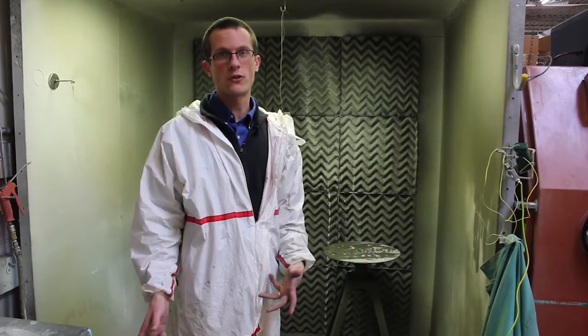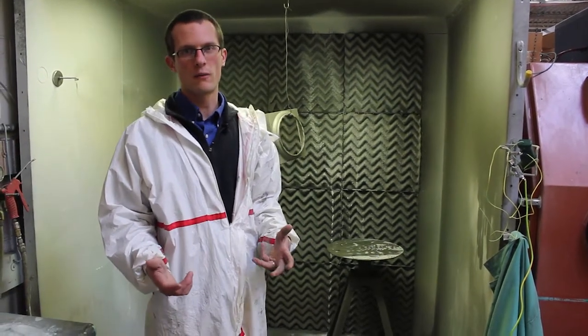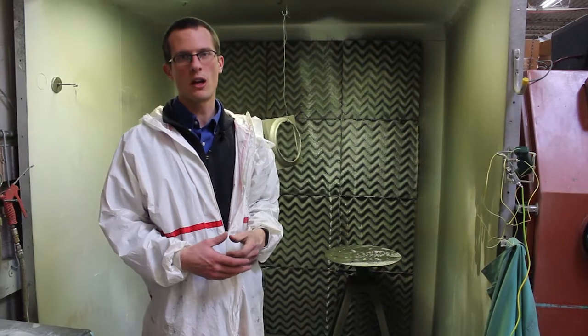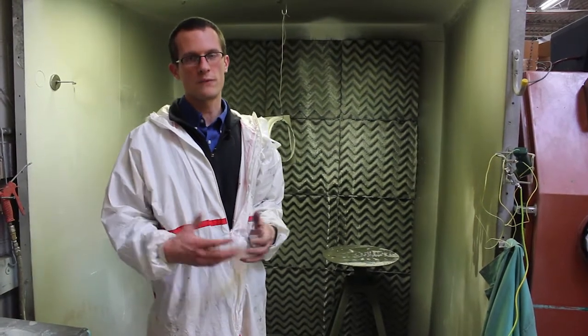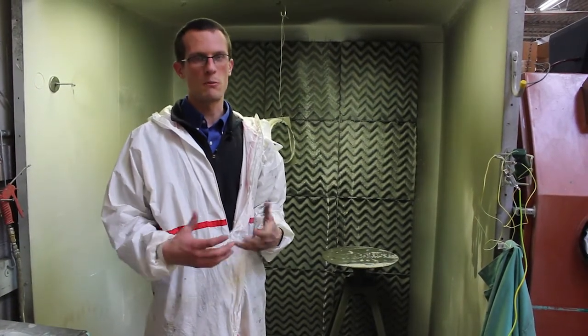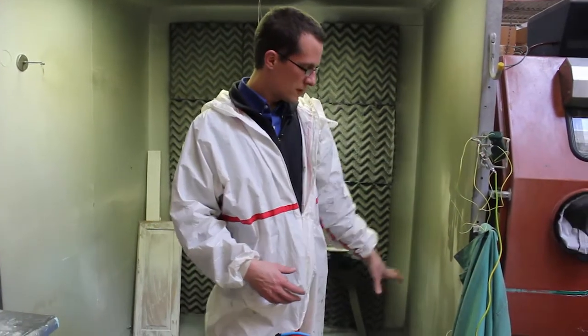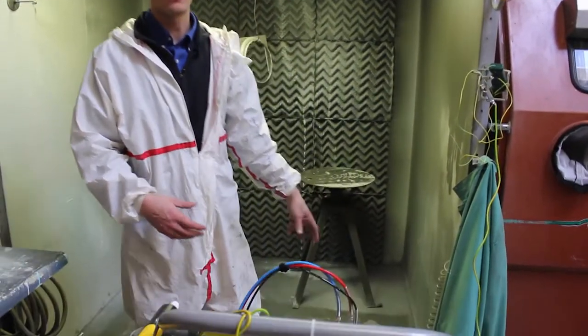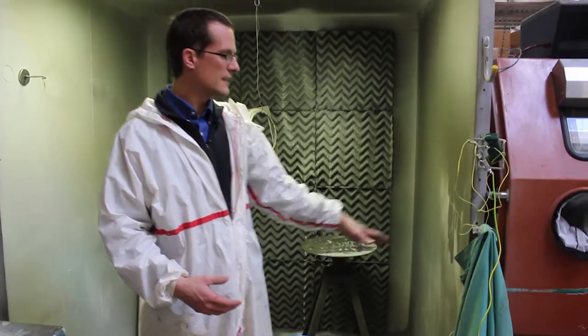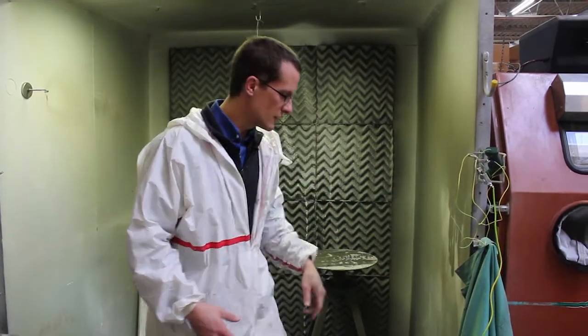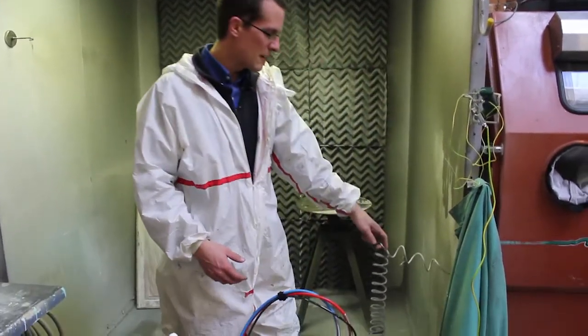Rubber isn't as conductive. So when you're wearing shoes, for example, you usually want to try to reduce the rubber sole on them or use a grounding strap so that they're able to be more conductive. So this booth is metal and it's secured into the earth with some screws. So we've tested it. The booth itself is actually relatively grounded. We have a grounding cable here.